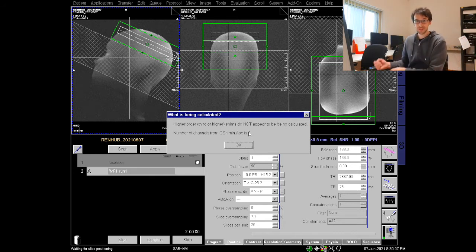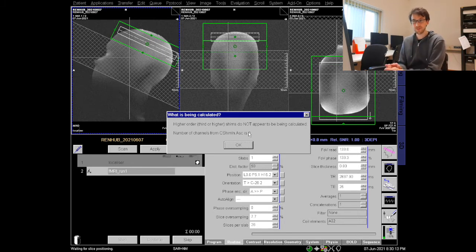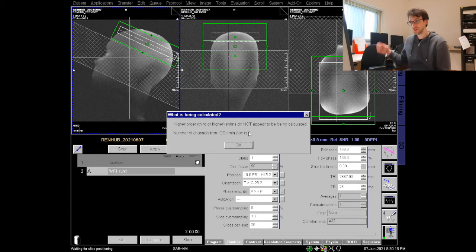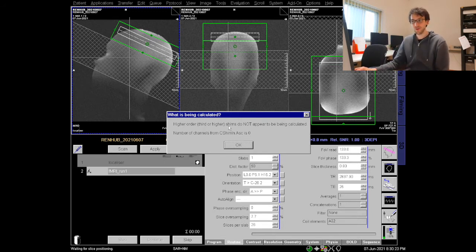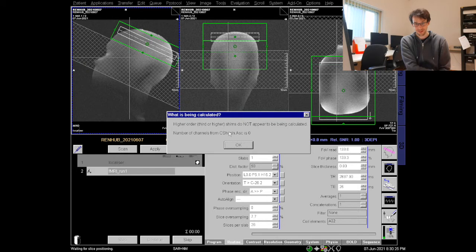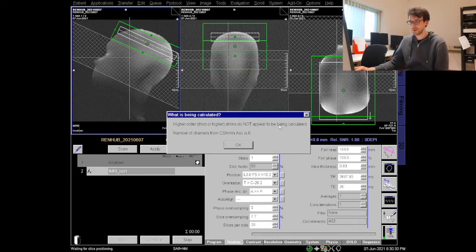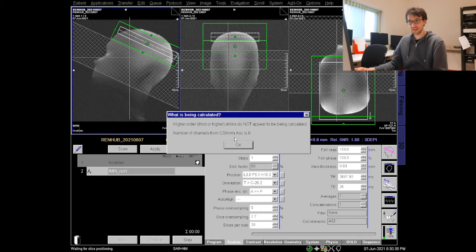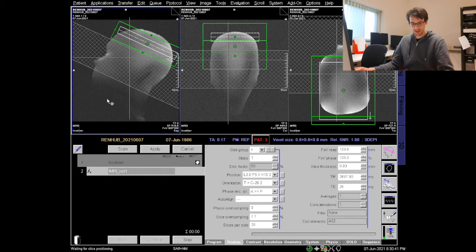This is how the system should be when you approach it and start your experiment. If this is not a zero, somebody scanning before you screwed up and didn't switch it off again and this is really something that we should avoid because other people who are not aware of using the third order shim and don't use it actually might end up with a worse second order shim if they're not aware that the third order shim is enabled. So always switch it off after you're done with your experiment and I will show you again when we are done here with our little tutorial. Everything's in order now and I'm starting the experiment and the shim, the number of channels is zero.